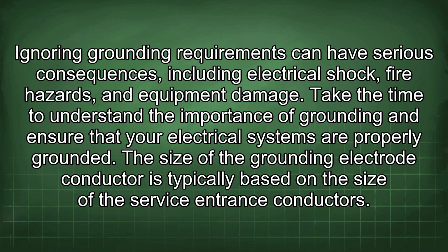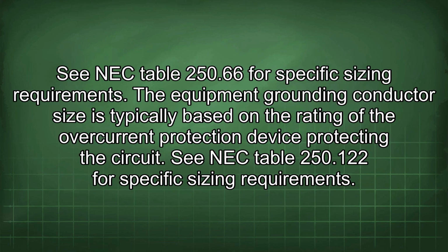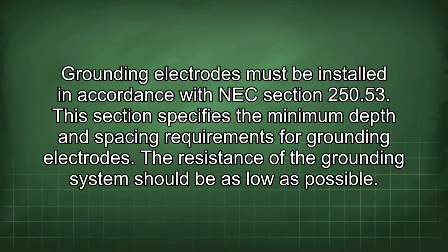The size of the grounding electrode conductor is typically based on the size of the service entrance conductors. See NEC Table 250.66 for specific sizing requirements. The equipment grounding conductor size is typically based on the rating of the overcurrent protection device protecting the circuit. See NEC Table 250.122 for specific sizing requirements. Grounding electrodes must be installed in accordance with NEC Section 250.53. This section specifies the minimum depth and spacing requirements for grounding electrodes.